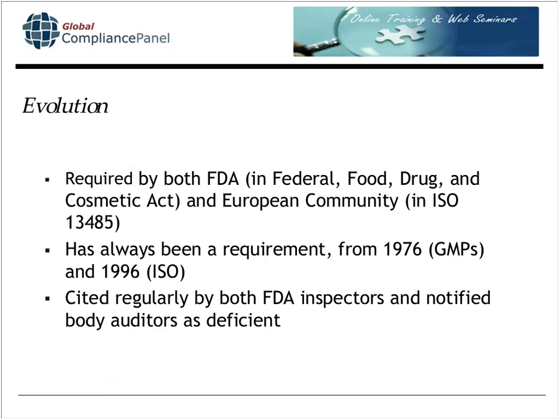Complaint handling is required by both the FDA in the FD&C Act and the European Community in ISO 13485. Complaint handling has always been a requirement from the first iteration of the GMPs, which is the QSR now, back in 1976, and the first iteration of ISO 13485, in which the 1996 version, the overwhelming majority of ISO 13485 just said, for example, Section 2.1, look at ISO 9001. Section 2.2, look at ISO 9001. The first iteration of ISO 13485 was maybe 7 or 8 pages total because it referenced exclusively ISO 9001.